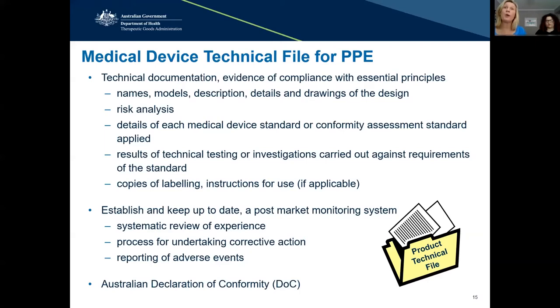So if you choose to apply the requirements of a standard and demonstrate that you meet it, you can satisfy the essential principles. If you choose a different route for demonstrating compliance, you need to justify that the processes applied are what we consider state of the art. You can't apply a lower standard, which is why, even though those standards aren't mandatory, they're useful.